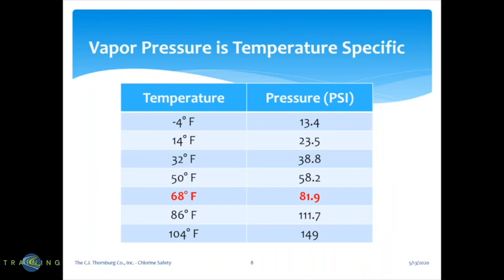Vapor pressure is temperature specific. If you have a cylinder at minus 4 degrees Fahrenheit when it's very cold, the pressure is very low — 13.4 pounds per square inch. As the temperature gets hotter, obviously the pressure builds. At 68 degrees Fahrenheit, which is ambient or normal temperature, the standard pressure is 81.9 PSI. On a very hot day at 104 degrees Fahrenheit, your pressure is going to be very high — 149 pounds per square inch. This is useful information for your plants when temperatures are very high.